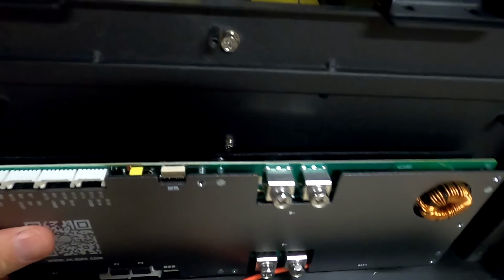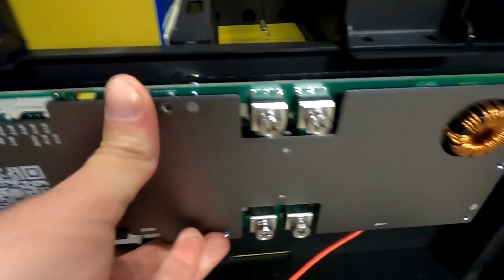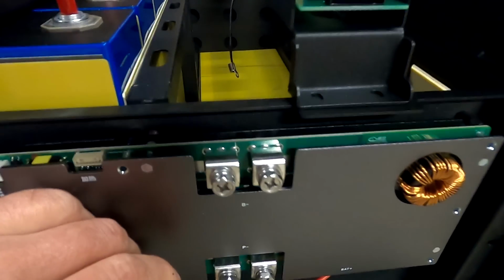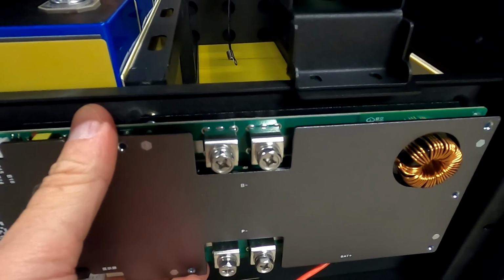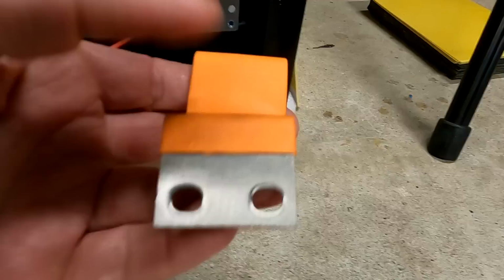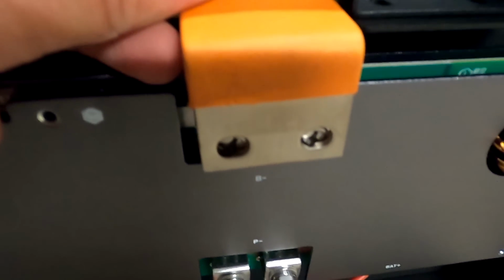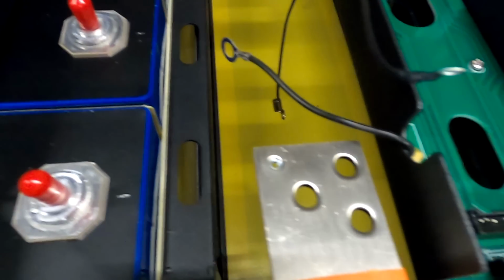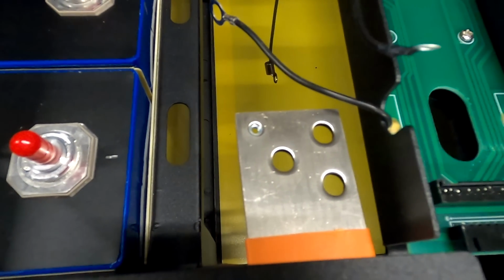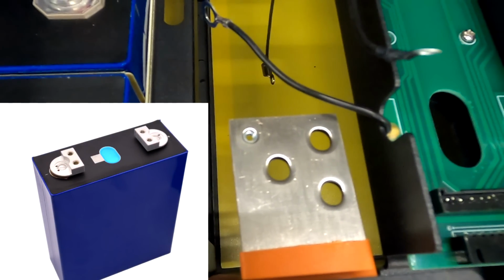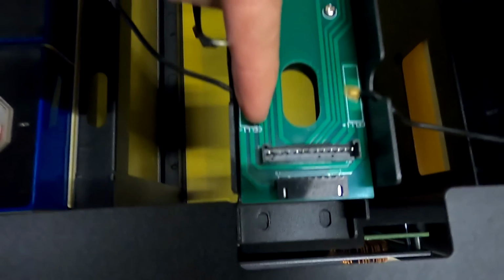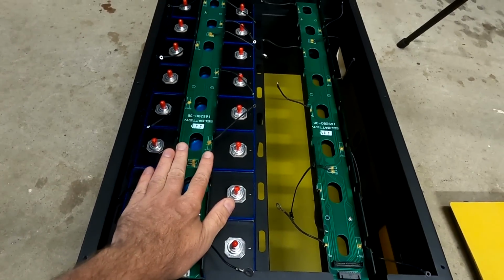So mounting the BMS here on the compression plate. The JK goes this way and has the B negative terminals up here. Are you holding here? No, probably not. I think they want me to use this bus bar they sent. See these two holes? They line up perfectly with the JK BMS. And then we've got these three holes here on top, so we can use batteries with double pole terminals or single pole terminals. Pretty clever. So main negative is over here, and the plug connectors go on the right hand side of the box, where it says cell number 1. So A goes over here, B goes over there.